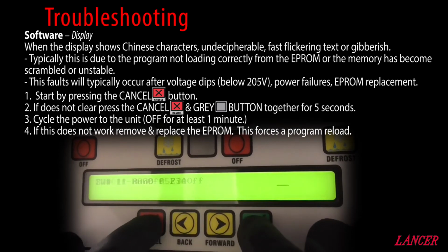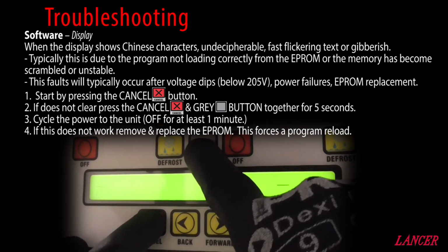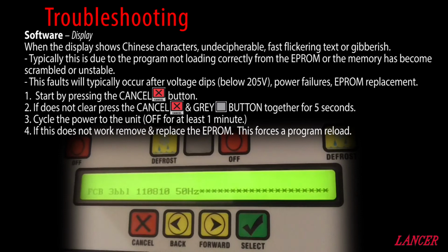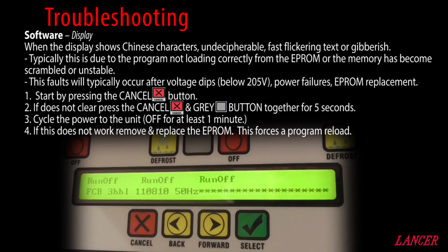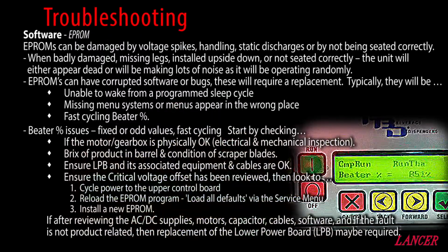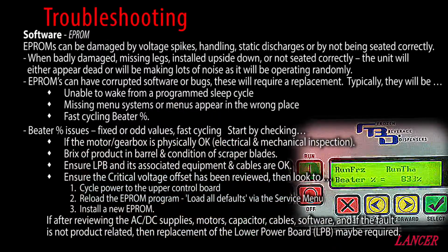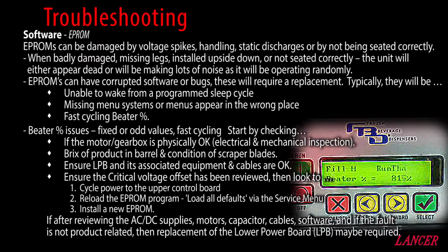If it does not clear by pressing the cancel button, then try holding down the cancel and grey button together for 5 seconds. Then try cycling the power to the unit for at least 30 seconds. And if this does not work, then try removing and then replacing the EEPROM, which forces the program to reload. EEPROMs can be damaged by voltage spikes, handling, static discharges, or by not being seated correctly.